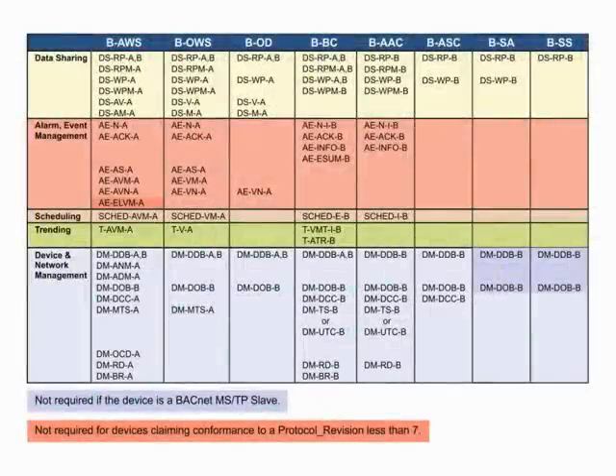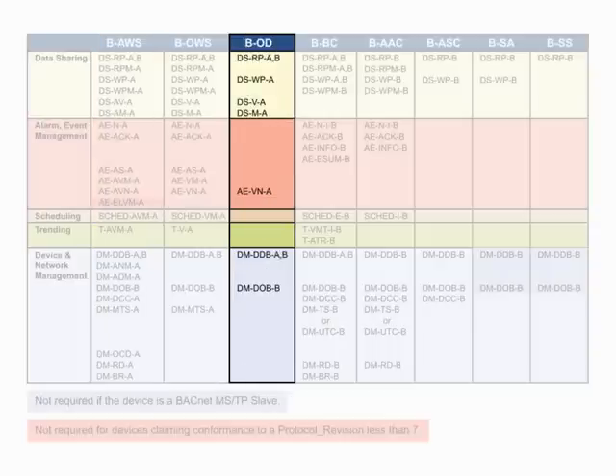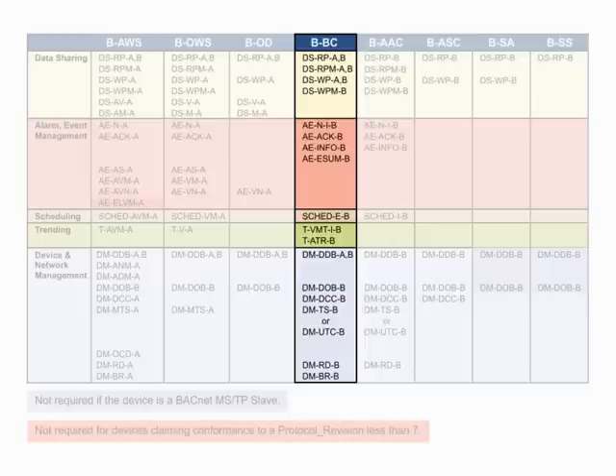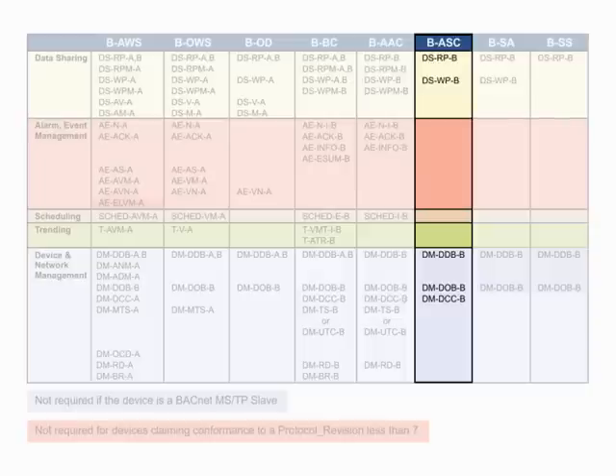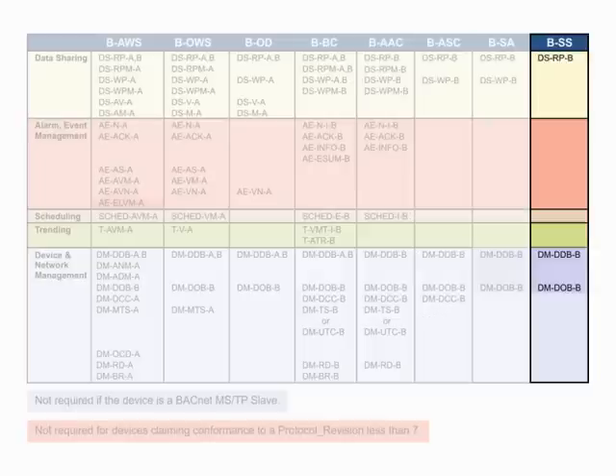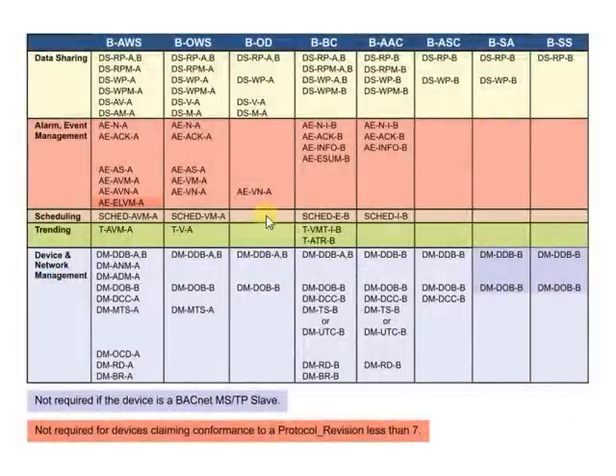There are currently eight device profiles: Advanced Operator Workstation, Operator Workstation, Operator Display, Building Controller, Advanced Application Controller, Application Specific Controller, Smart Actuator, and Smart Sensor. You will notice a list of BIBs under each of the BACnet device profiles. This listing represents the minimum number of BIBs required for a device to be classified accordingly.